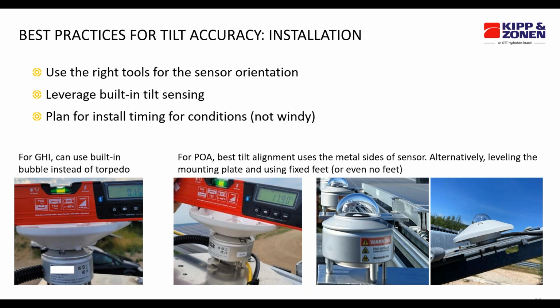And again, if you have a laptop and a connection to the digital sensor with that 2-axis tilt, while you're putting something in POA, you can measure the east and west and north and south orientations on your modules, or even a few modules, and average them, because not all the modules point exactly the same direction. And then use that 2-axis tilt to point the pyranometer in the same orientation as your modules are.